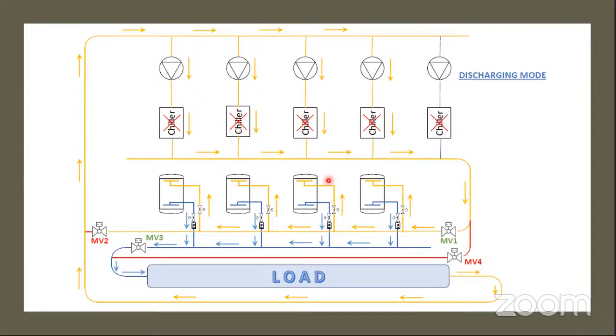Let us check the path here. These pumps are operating, and let us in fact start from here. This chill water is being drawn here and sent to the load. The water became hotter, warmer, and it is going back to the entrance of the primary pump. They travel across the chiller, they come here, and from this header they enter into the tank top. So there is no valve position changing as such. So this is discharge mode.